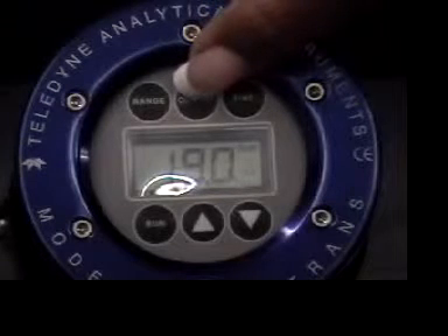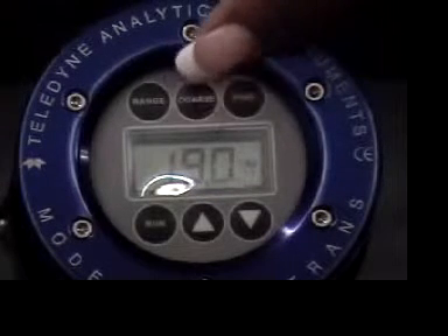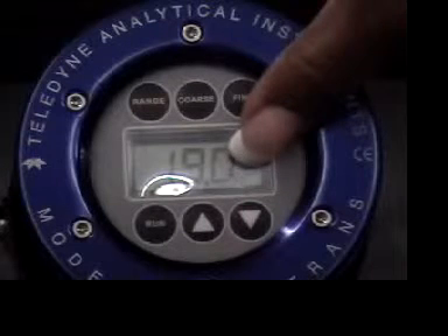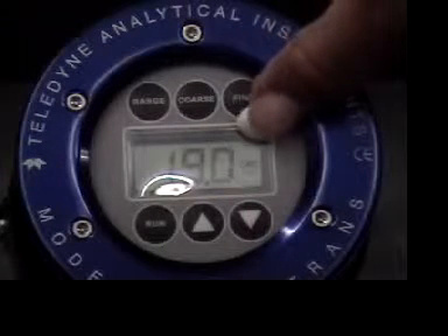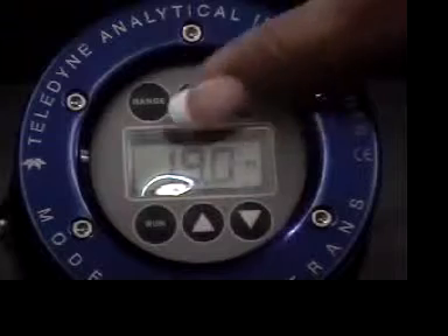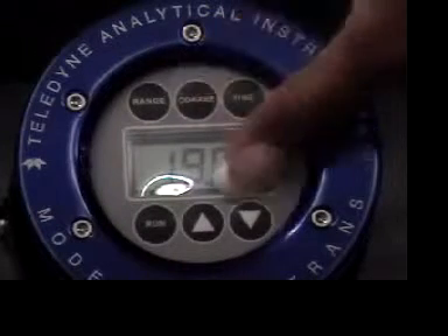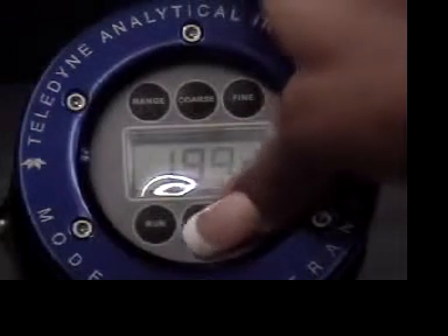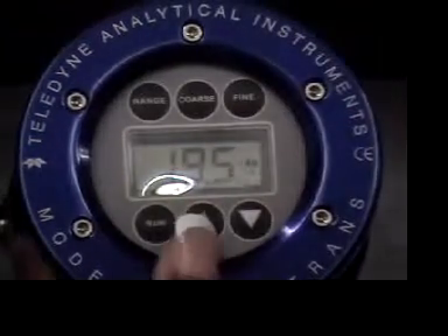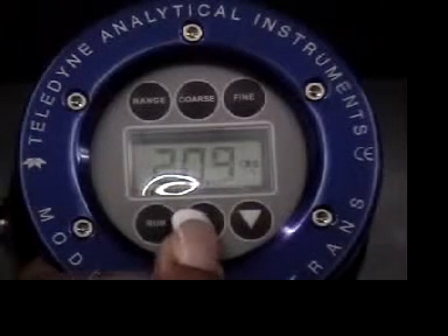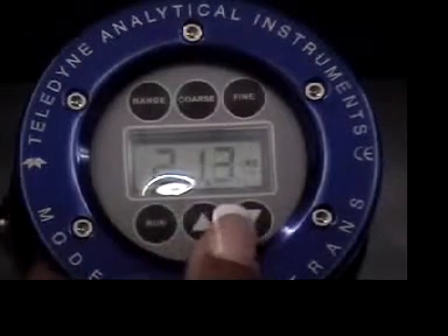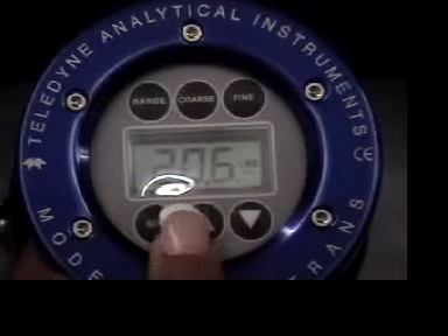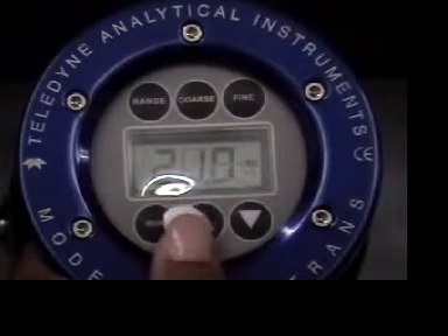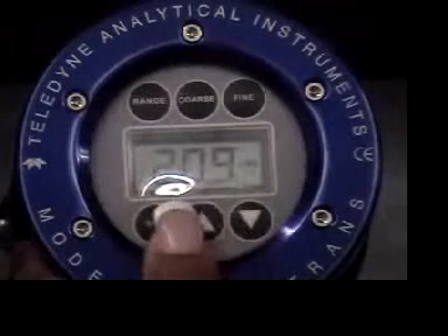Now to start calibration, you press the coarse button. When you do that, you'll see CRS over your percent sign. The RUN has disappeared, and now you're in the coarse adjustment. You want to do this right away. Once you press the coarse button, adjust your oxygen to read whatever your span gas is. In this case, I am doing an air calibration, so I'm looking for a 20.9% oxygen reading. You can go as close as you can, and right now I'm between 20.9 and 21%.